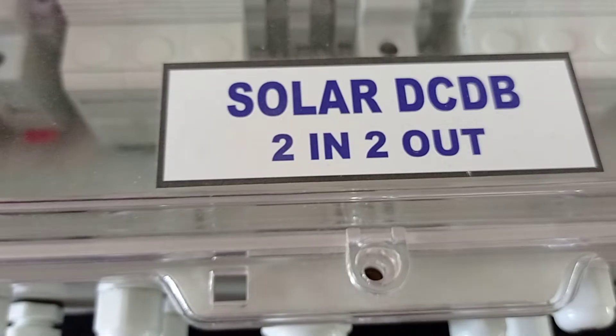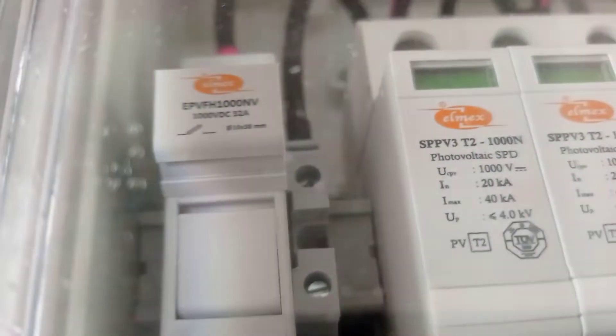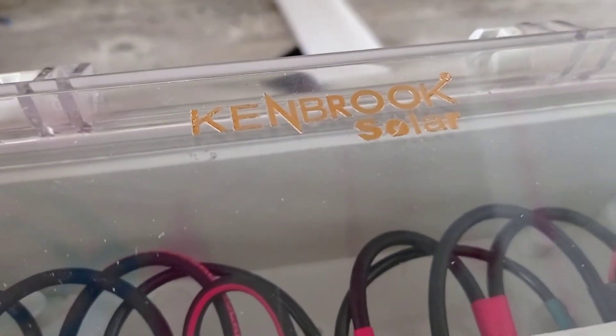This is a two-in two-out DC DB with the Elmex — this is an Indian brand — 1000 volt SPD, and Elmex 32 ampere fuse holder. The fuse will be 16 ampere, and this is our branding.